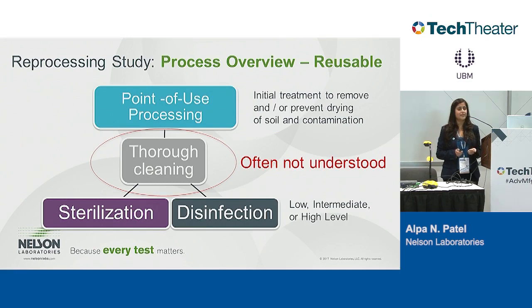if your devices are thermolabile, then you can't do sterilization, and you would have to do disinfection validations. For example, let's say we have the slide in the OR room. We can't sterilize this, so we would have to do a disinfection validation. It doesn't come in contact with blood or anything. It's just sitting there, so we would consider it as a low-level disinfection validation.